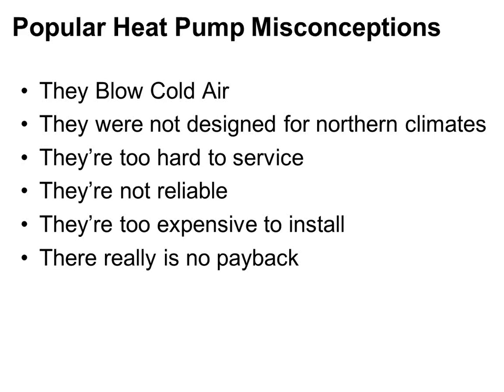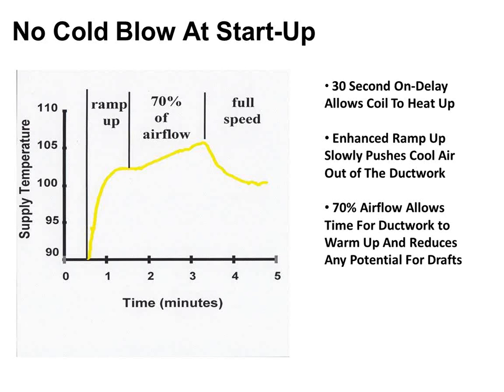So in regards to the cold blow thing, that's been easily solved by all the variable speed heat pump manufacturers, both residentially and commercially. There's a couple different things that can be done to mitigate that. So one thing is that when we first turn on a heat pump, right, instead of turning the indoor fan on at the same time and blowing the cold air around, what we first do is we allow the indoor coil, which is now the condenser coil if you recall, to start heating up, and then once it gets up to temperature, then we turn on the indoor blower to run air across it.